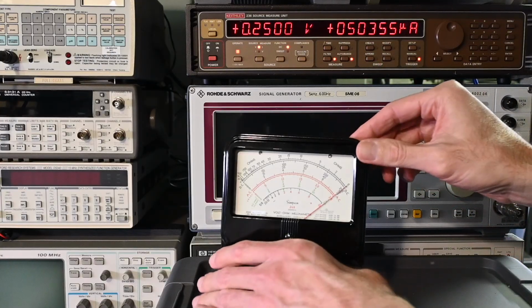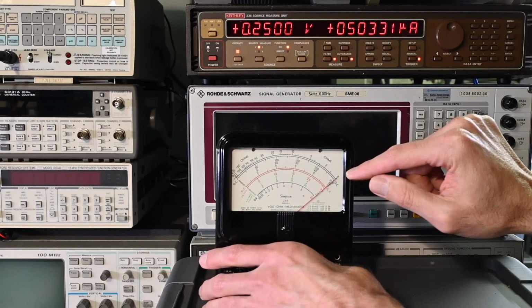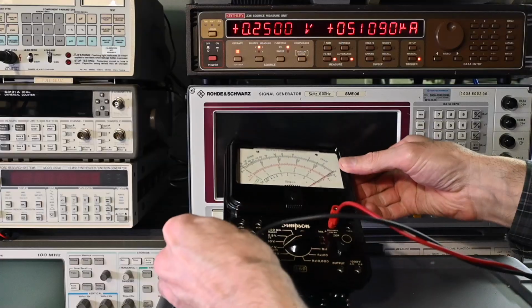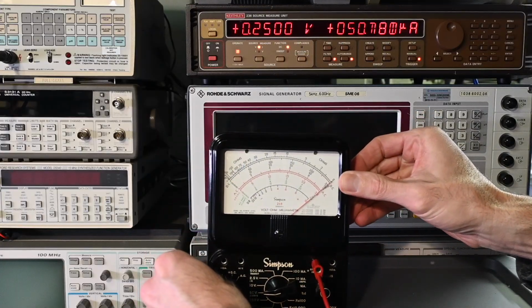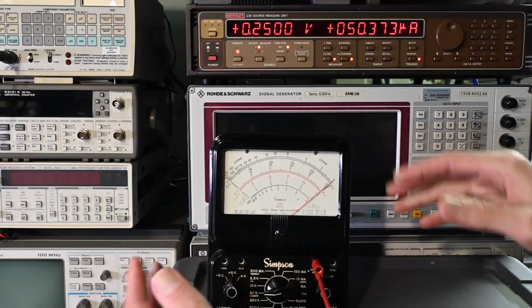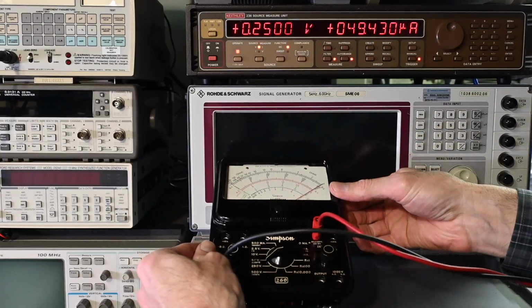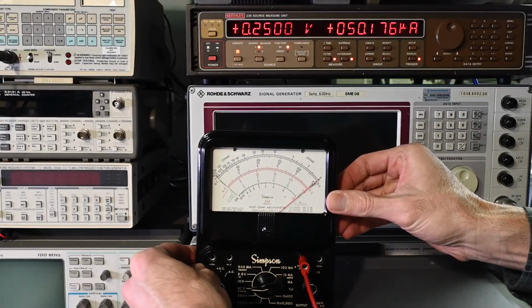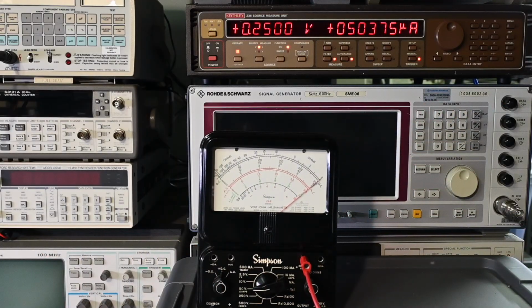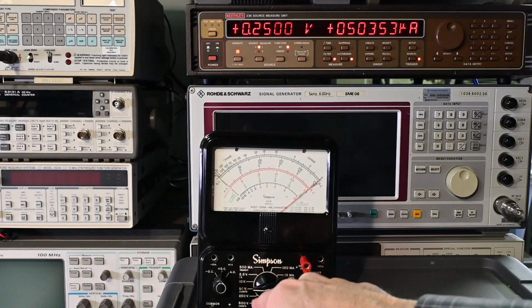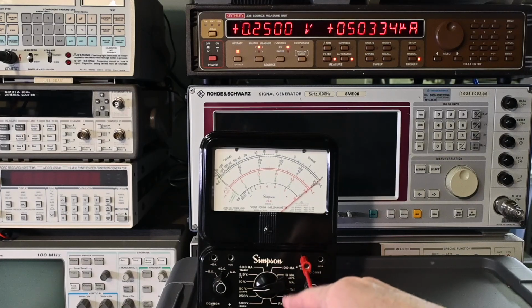So this looks very good. It's basically looking spot on right there, and again, I'll double check it, and also I need to check it with the meter laying down flat like this as well, just to make sure that it's indicating, because most of the time the meter is used laying on its back or with the handle as a tilt stand. It's angled just a little bit. But all right, so it's looking like it's working correctly. Very, very happy with the results so far. And when I get the calibration touched up and everything's looking good here, then we'll go through and double check the other ranges for the DC voltages. We'll check the ohms function and DC amp ranges as well. And then we need to do the AC calibration.